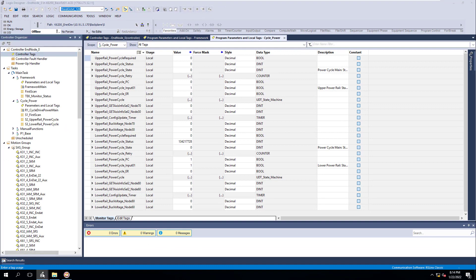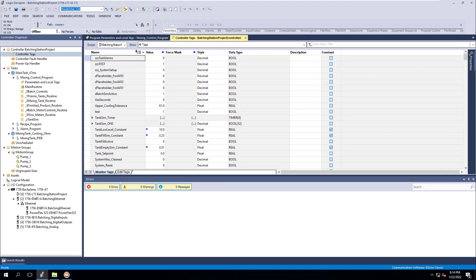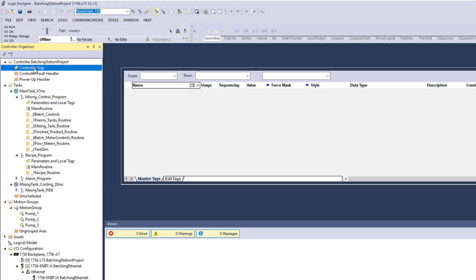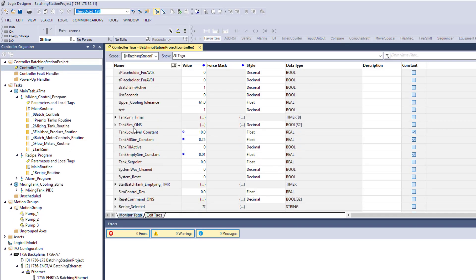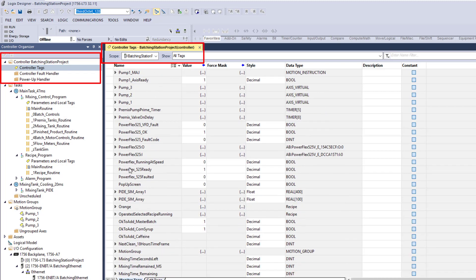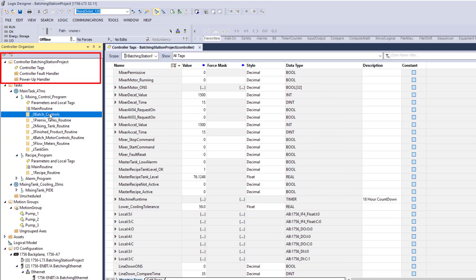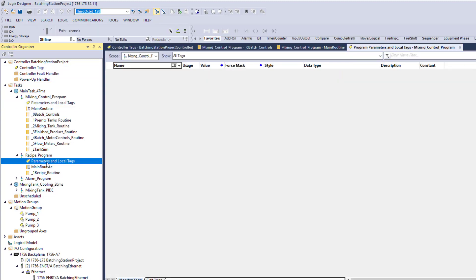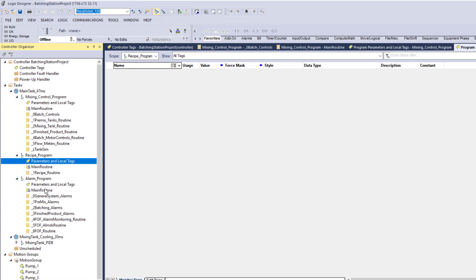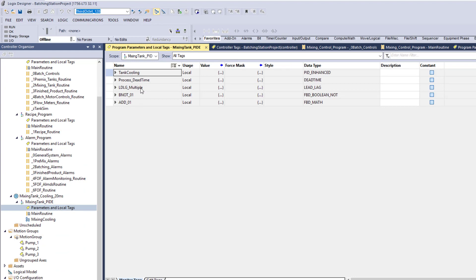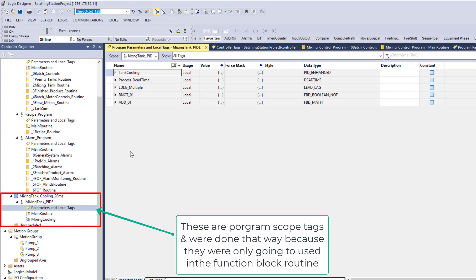Let me show you another program — the batching system I have right here. I made all of my tags in controller scope. Every one of my tags is in controller scope, and the reason I did that is so I can have easy accessibility. If I look at program scope tags, I have zero program scope tags. And right here I do start making program scope tags, but I'm not using these inside of my HMI.